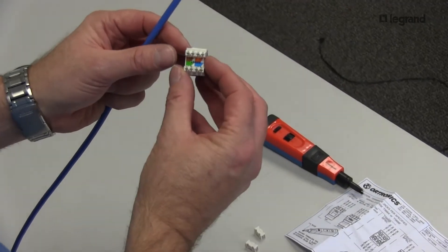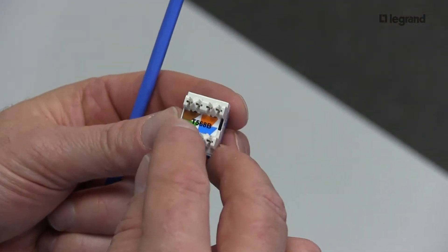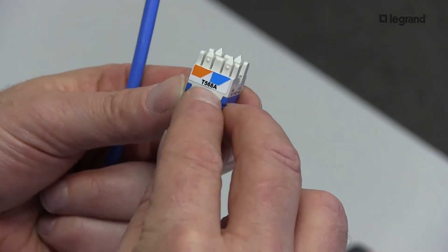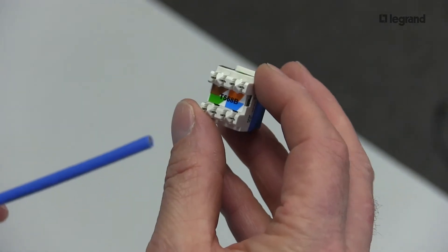So I'm working with a Category 6 KS jack, and if you notice, there are two different color standards. There's a 568B in the center and a T568A on the outside. So be aware of what color standard you're wiring for the rest of your building. Today I'm going to show a 568B.